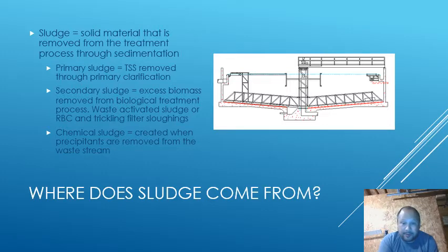Raw or primary sludge settled by itself in a primary clarifier can be anywhere from 2 to 7 or 8% solids, depending on how the clarifier is operated.